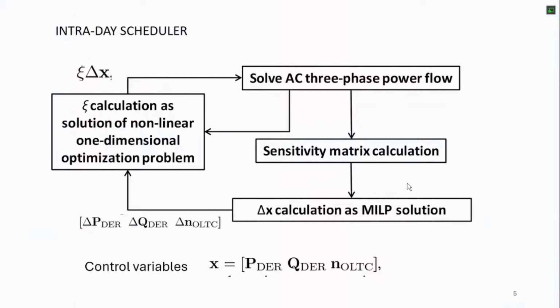I will try to show you that this relationship between the variation of the control variables and the variation of our variables, the voltages in particular, but also the currents in the branches, can be directly calculated from the results of the power flow. In particular, by using the Jacobian matrix, which is in general included in the solution of the typical three-phase power flow because it uses Newton-Raphson. So by using this matrix, we have a relationship between what we need to control and our possibility to control, the control variables.